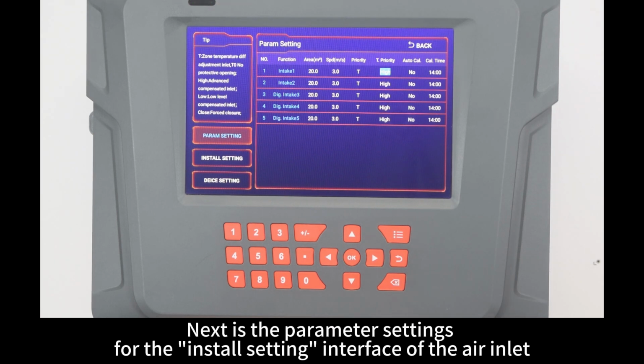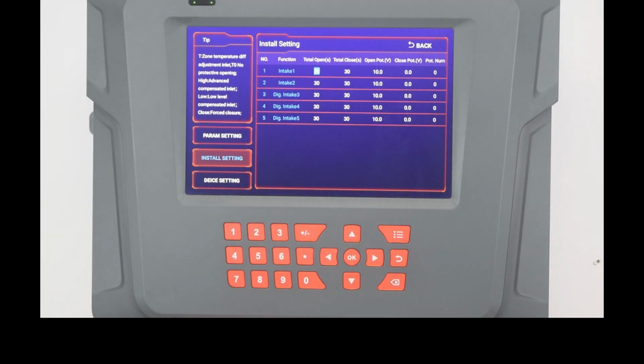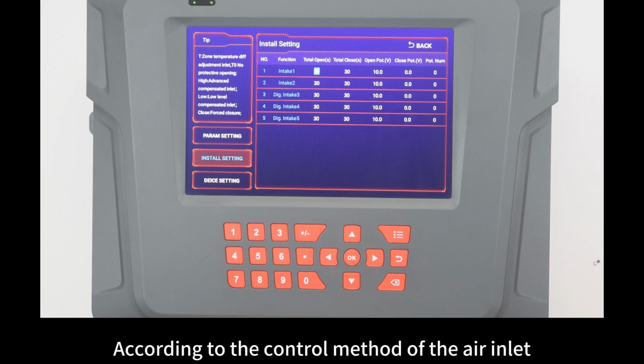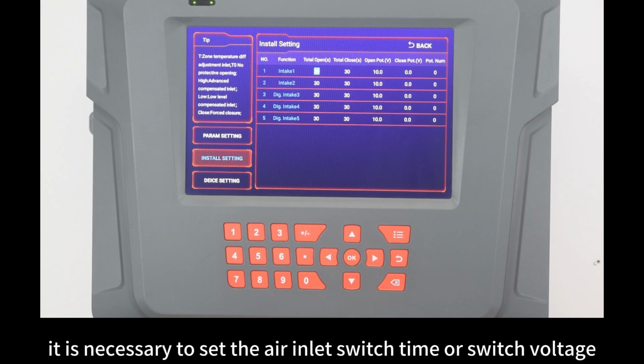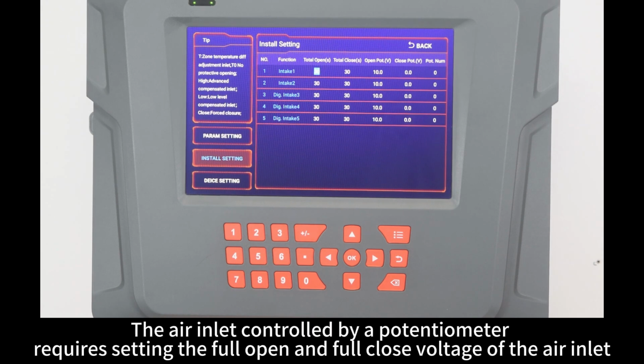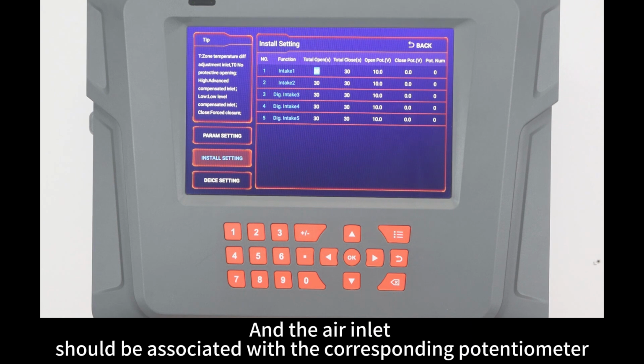Next is the parameter settings for the install setting interface of the air inlet. According to the control method of the air inlet, it is necessary to set the air inlet switch time or switch voltage. The air inlet controlled by a potentiometer requires setting the full open and full close voltage of the air inlet, and the air inlet should be associated with the corresponding potentiometer.